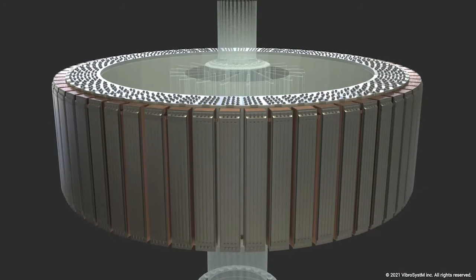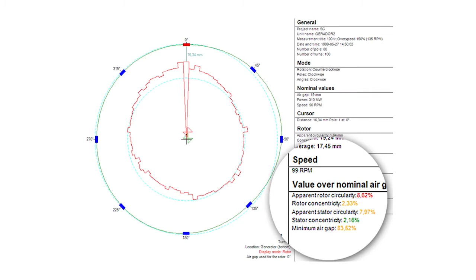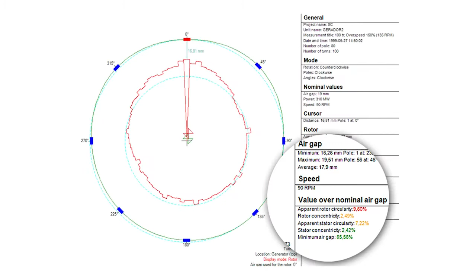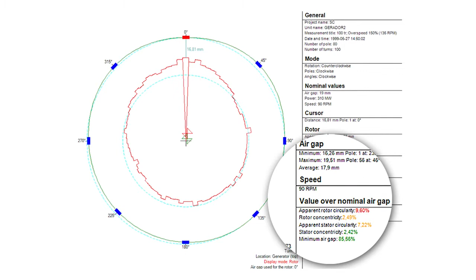Although it seemed to be doing what it was supposed to, it was in fact going back to a shrink fit. But the issue was that it was doing so at a speed that was way too slow. These particular units were designed to allow the rotor rim to float as the speed reached 110% of the nominal speed during an overspeed or a load rejection event. In this case, the nominal speed was 90 RPM, so 110% speed was 99 RPM.